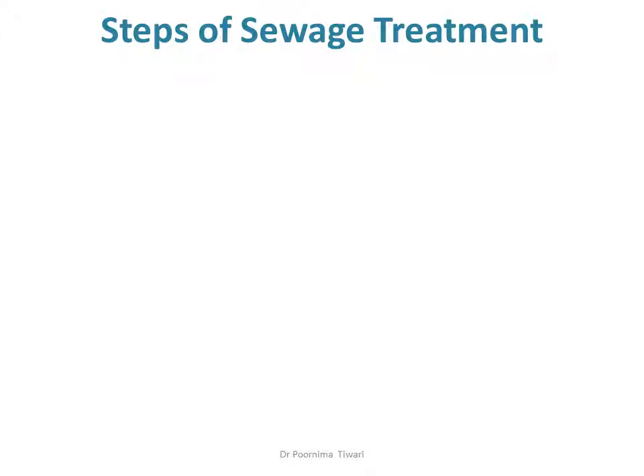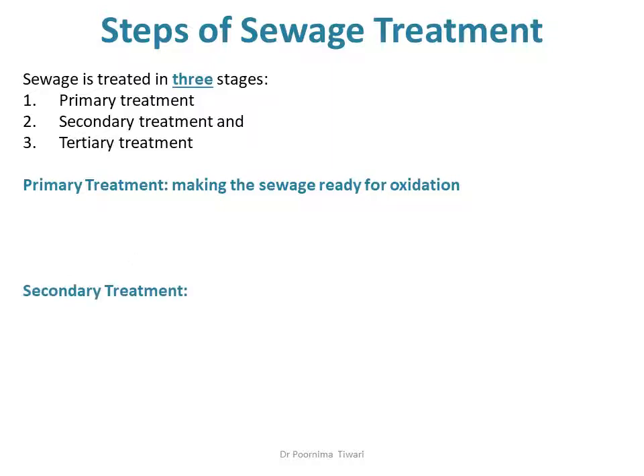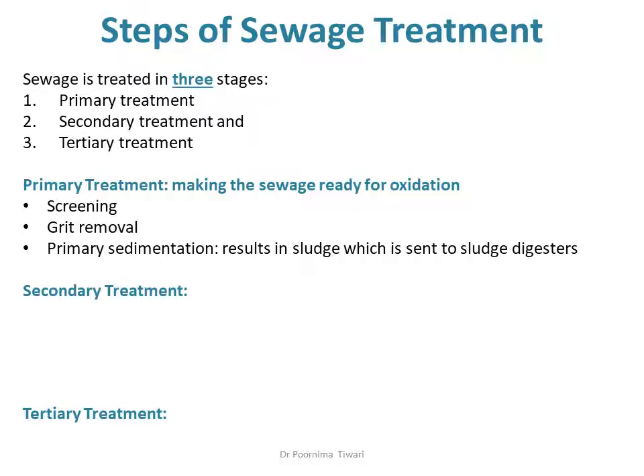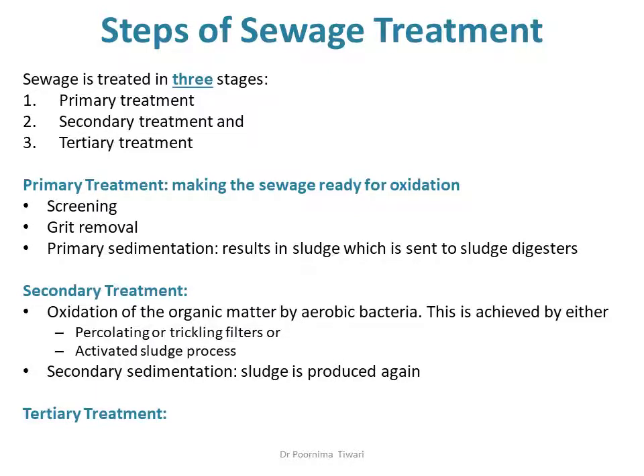The steps involved in the treatment of sewage: sewage is treated in three stages — primary treatment, secondary treatment, and tertiary treatment. Primary treatment makes sewage ready for oxidation. It consists of screening, grit removal, and primary sedimentation, which produces sludge sent to sludge digesters while the effluent goes to secondary treatment. Secondary treatment involves aerobic oxidation of sewage by aerobic bacteria, using either percolating filters or the activated sludge process, followed by secondary sedimentation. Tertiary treatment involves treatment of the sludge and disposal of effluent.